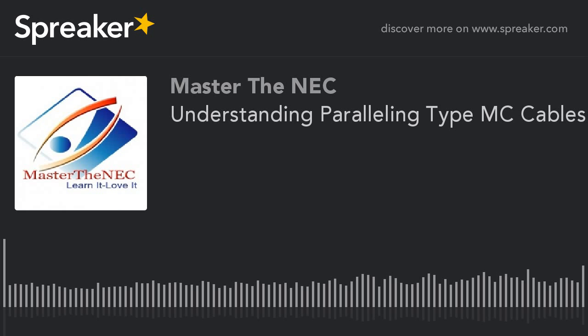Now, when I was an electrician out in the field and we had to do parallel applications, the product of preference at that time was an MC cable. And so when I was designing the MC cable show today, I got to think about all those questions I got about how come when I'm paralleling MC, and I have a larger overcurrent protective device than what I would have on a single cable, the equipment grounding conductor is too small.